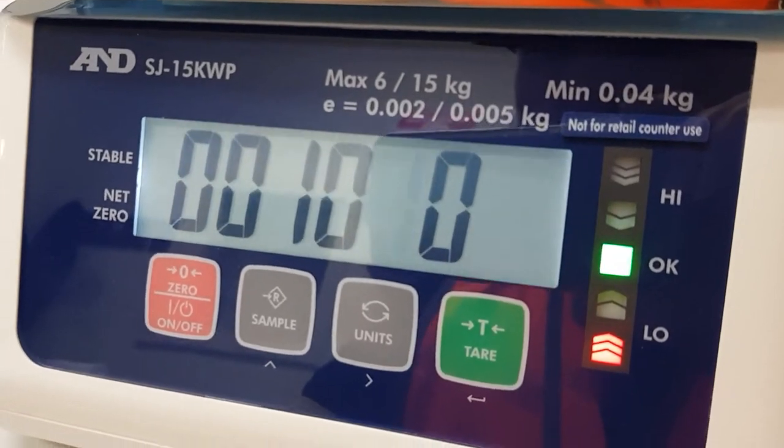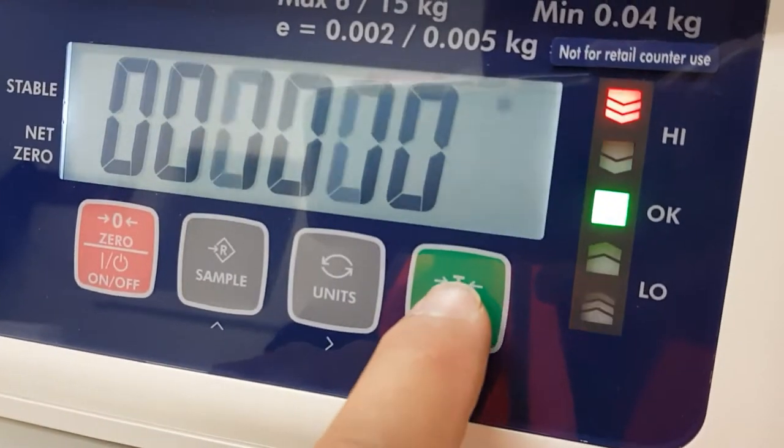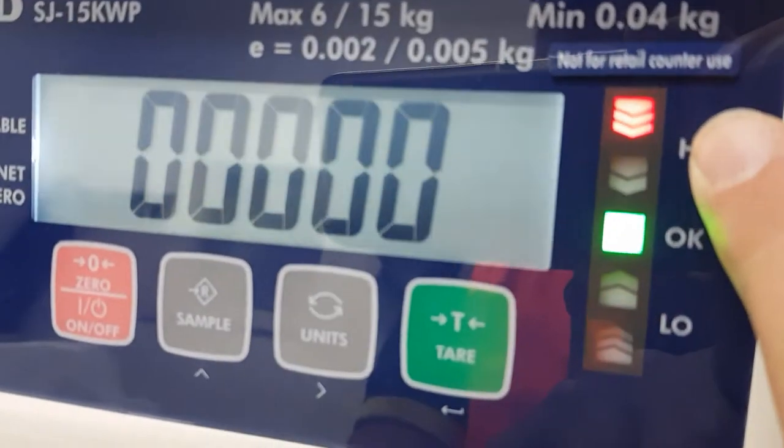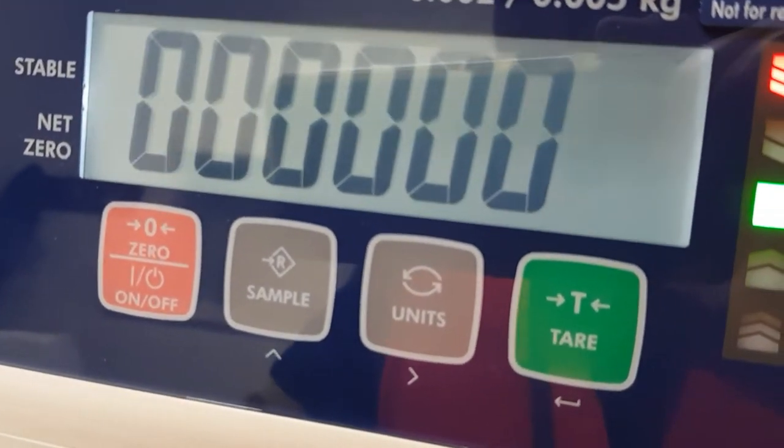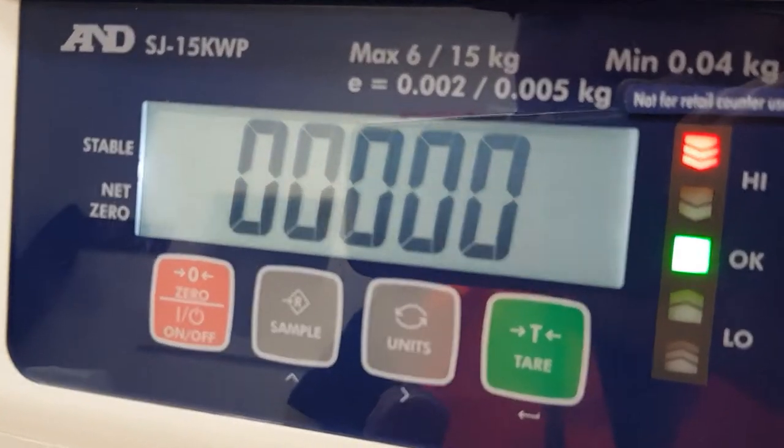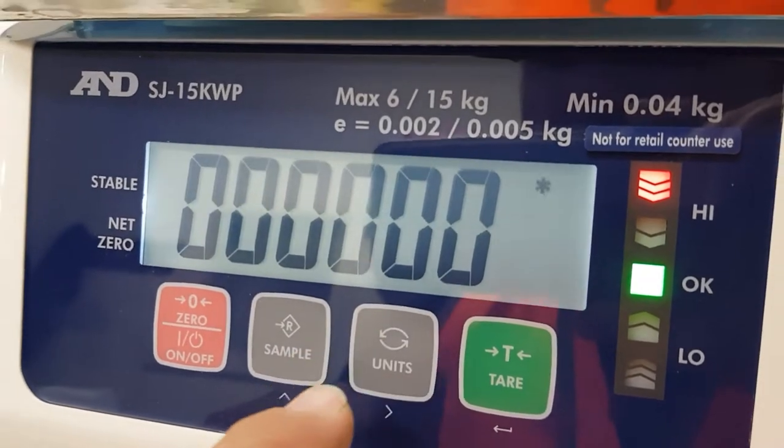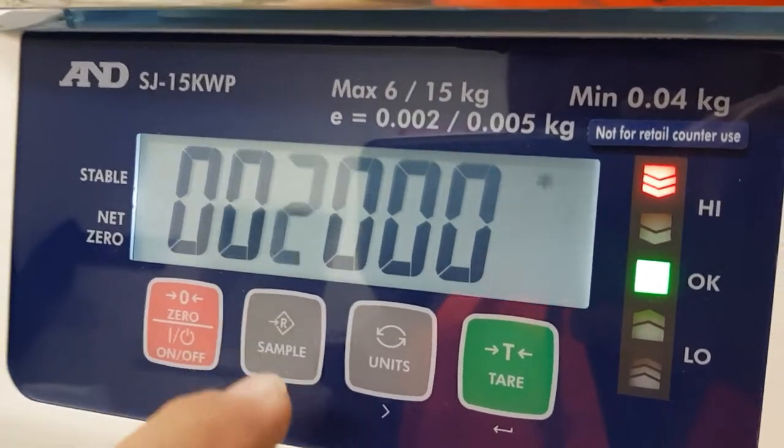Then when you're happy with that, you press the tare key. Now it goes to the high value setting. Again we've got all zeros on the screen. If we want to go to 2,000 grams as our high value, we go across until the thousands column is flashing, go up twice.